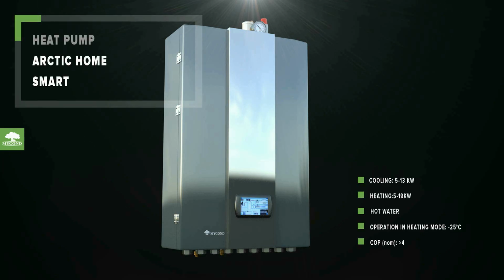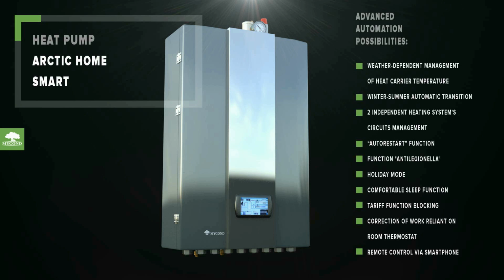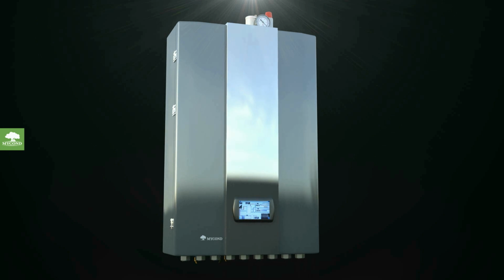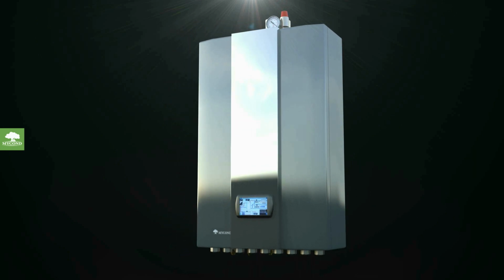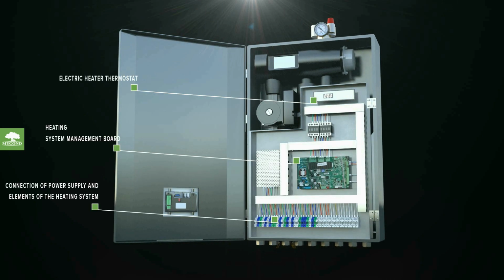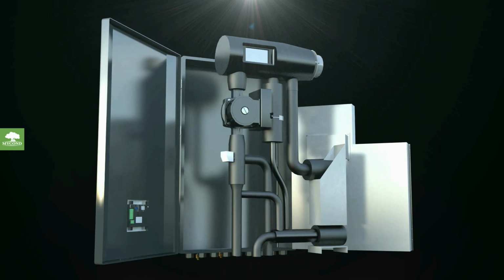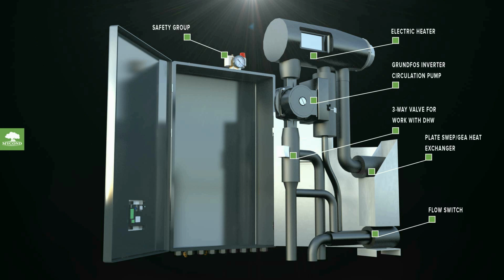In winter, Mycond Arctic Home Smart Series heat pumps work in the heating mode at temperatures down to -25 degrees and have advanced automation capabilities such as weather-dependent control, simultaneous management of 2 independent heating system circuits, anti-legionella function during hot water preparation and storage, correction of work via room thermostat, night mode and holiday mode, remote control from smartphone via internet. Heat pump's operation is controlled using a touch panel with English interface. You can control all the equipment parameters on a single screen.